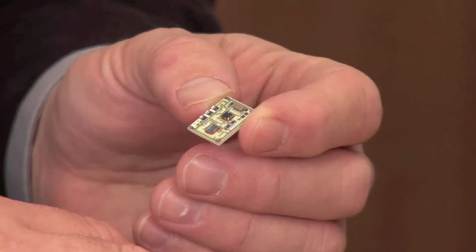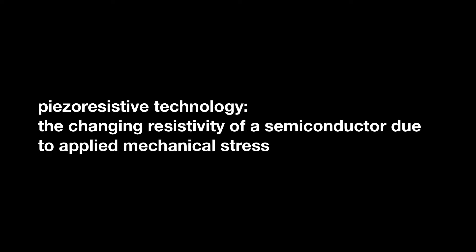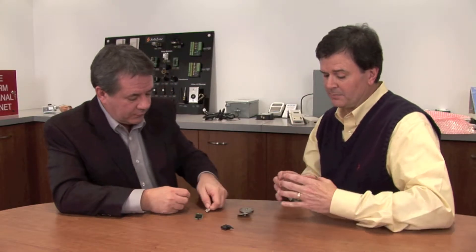What's this? That is a MEMS structure used in a lot of low pressure and high pressure sensors made today that utilize piezo-resistive technology. That's a little piece of glass — exactly. What they've done is taken a very small piece of glass and etched a diaphragm into it. They're creating a strain gauge so that when that diaphragm bends in one direction or the other, the resistance will change, and you measure that resistance and compute it back into a pressure.